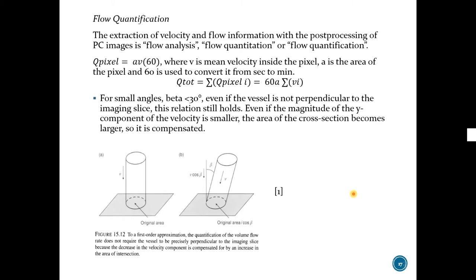I also want to mention flow quantification. It is a process of analyzing flow quantitatively. Q pixel is area times mean velocity. Sixty here is for conversion. And Q total is the sum of all Q pixels expressed like that. For small angles, beta smaller than 30 degrees, this can be estimated as a perpendicular vessel because the cross section area compensates the cos beta here.